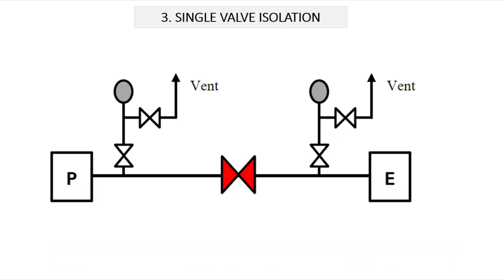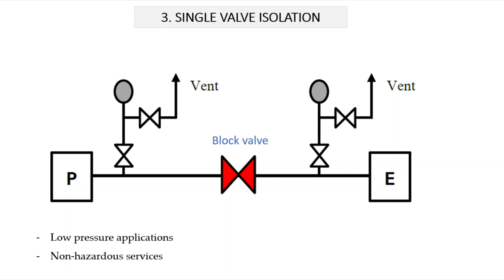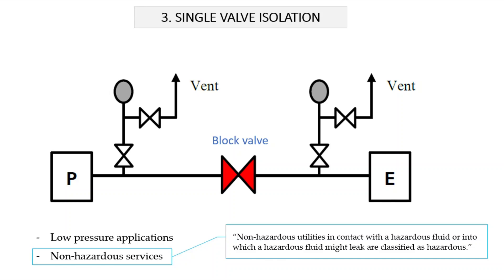The third and least secure type of isolation is single valve isolation, which does not have a bleed point. It can be achieved by simply closing a single block valve and is used for very low pressure applications and non-hazardous services. Classification of a line as hazardous or non-hazardous is very important, as in history some accidents happened where contamination of service lines with process fluid was overlooked, the line was mistakenly considered non-hazardous, and implementation of single valve isolation led to an accident.